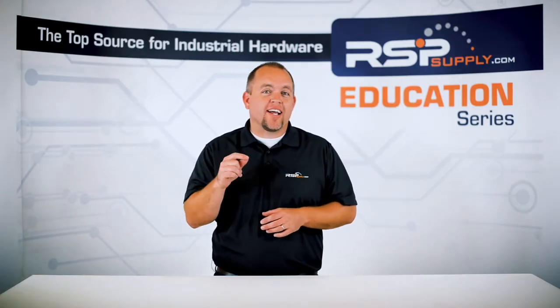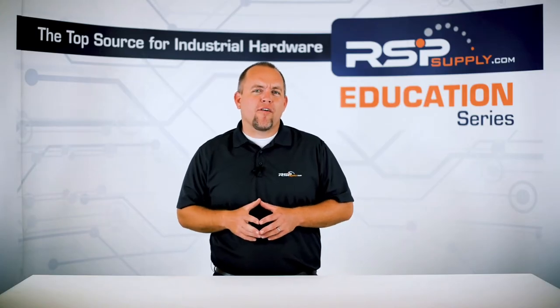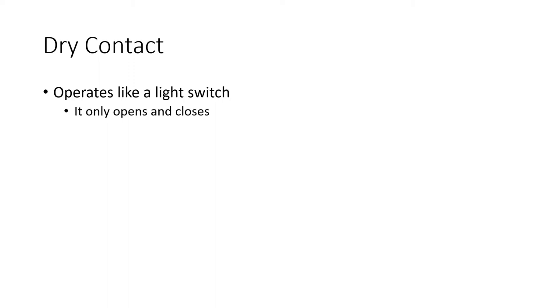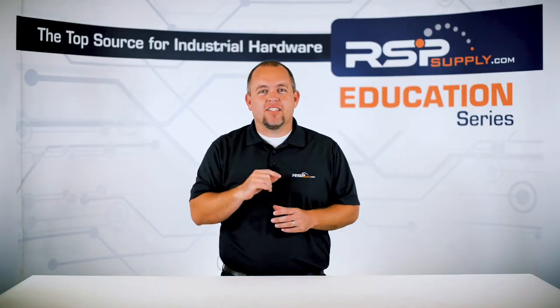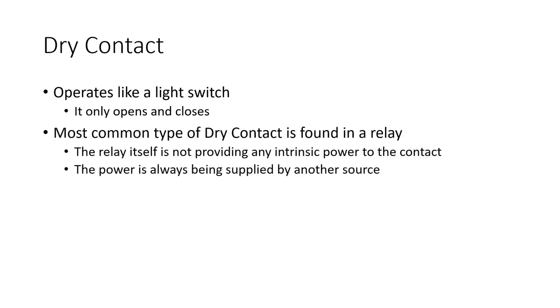Let's first start with the dry contact, as it is probably the more referenced type of contact out of the two. The easiest way to think of a dry contact is to think of a light switch. The switch itself does nothing except open and close. When the switch is closed, power that is being supplied by another source can flow through it. When the switch is open, power is interrupted and can no longer flow. This is the only purpose of the switch — this, in essence, is a dry contact.